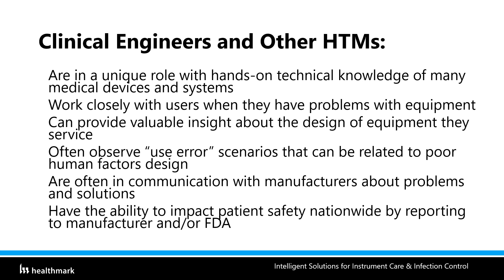But in addition to that, prior to 1992, which I'll talk about in a little more detail, some of that information was just between the technician and the receiver of the call at the medical device manufacturer. Sometimes you would call one technician at the service call and get an answer, then call somebody else. Really, even these medical device manufacturers didn't have a good system to keep track of all those calls to make some sense out of them, for example if there's a design issue with that technology. But we have the ability as HTM to report these to the FDA, to a database that we can look into.